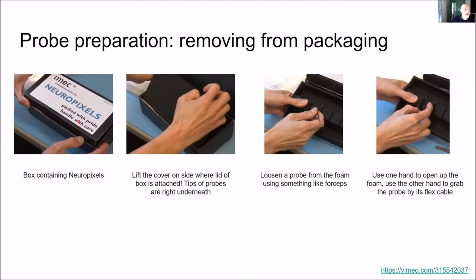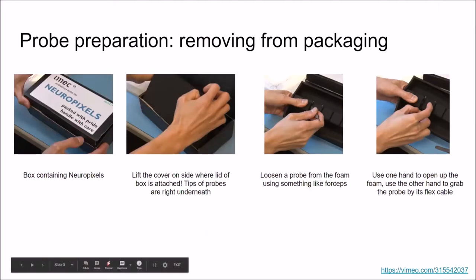Your audio is fine, but your video is interrupting. So I'm going to stop your video. Okay, thank you. If you open the box, you need to remember that the shanks will be facing the lid or where the lid is attached. So you really want to lift the lid this way and not the other way. Otherwise, you'll break your probes or it's highly likely that you will.